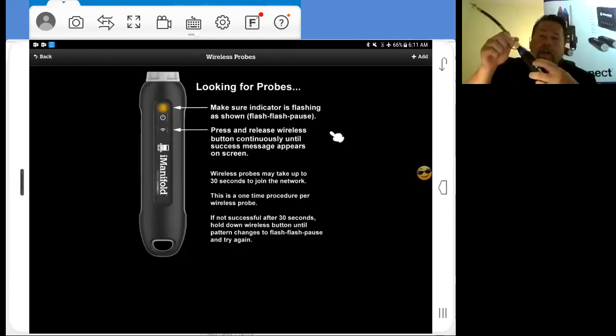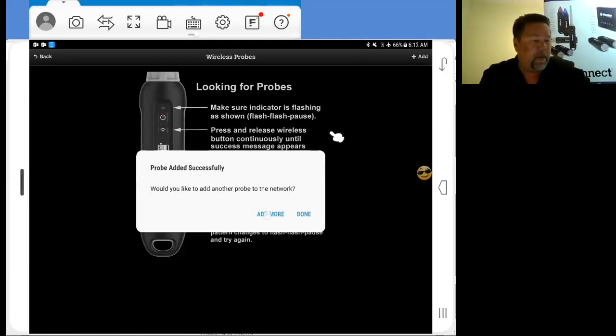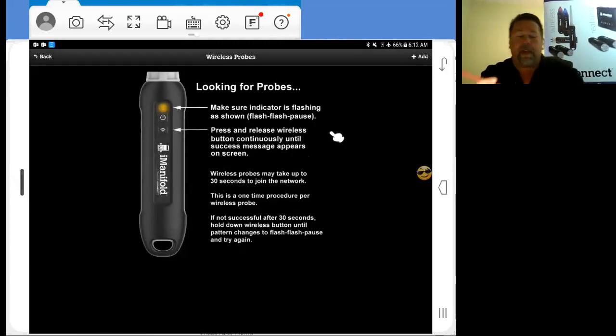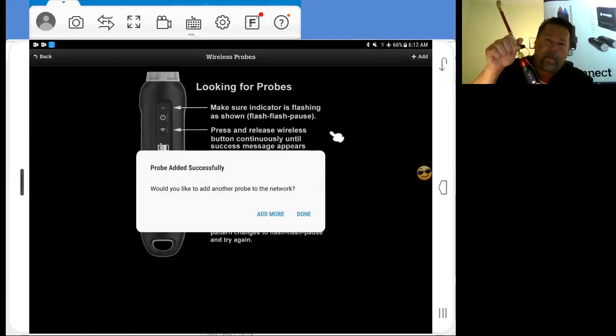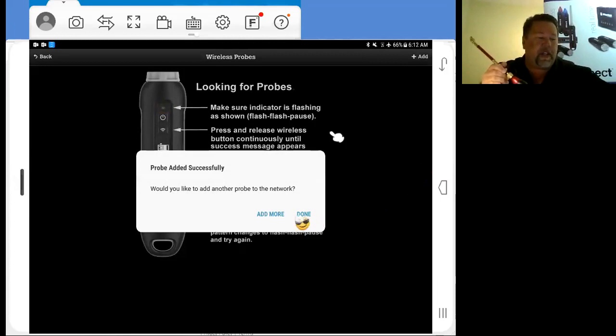So we're on, our lights are correct. We're going to pair up. And I've got one more probe in my particular system here. This is my high side. The same little fitting here. If I need to subtract refrigerant, I've got it. Powering up. Transmit. And there we are. Now this was the last probe in my system, so I'm going to go ahead and select done.